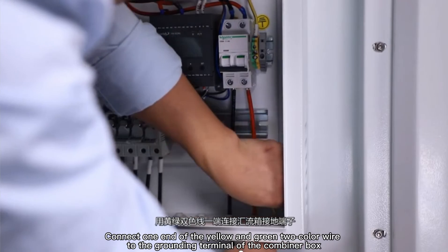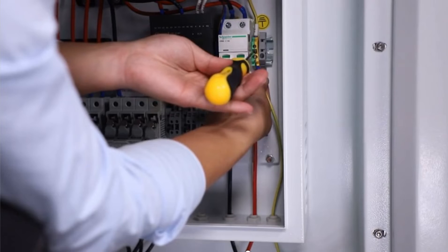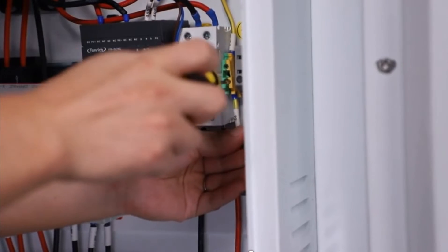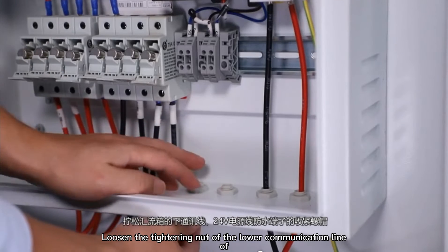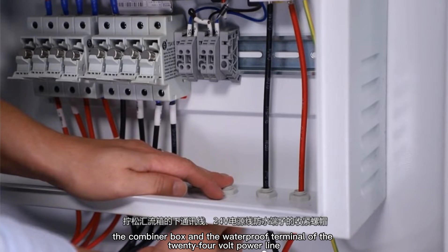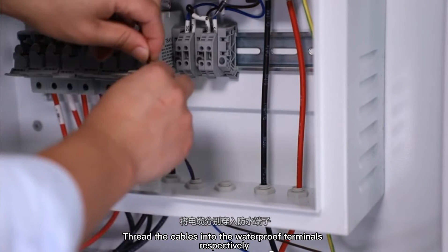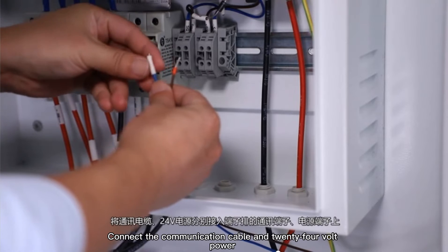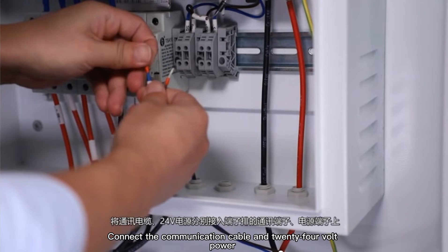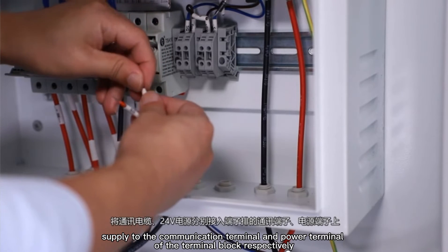Connect one end of the yellow and green bi-color wire to the grounding terminal of the combiner box. Loosen the tightening nut of the lower communication line of the combiner box and the waterproof terminal of the 24-volt power line. Thread the cables into the waterproof terminals respectively. Connect the communication cable and 24-volt power supply to the communication terminal and power terminal of the terminal block respectively.